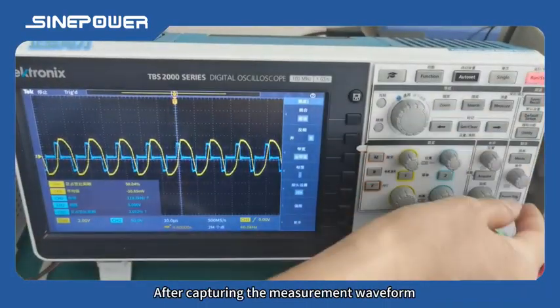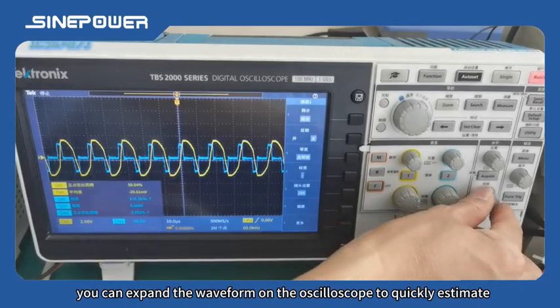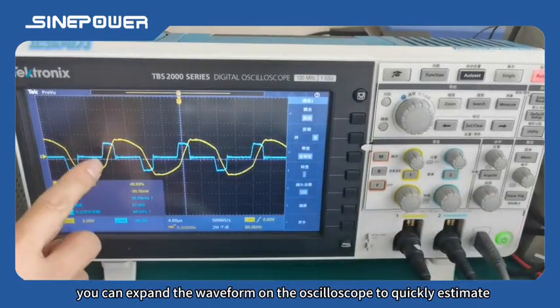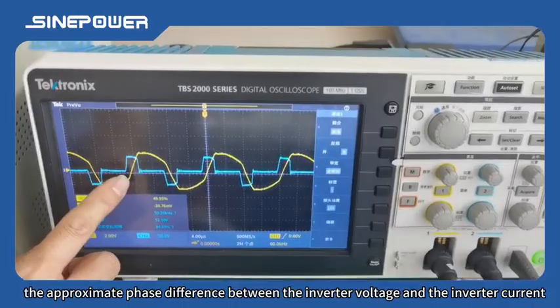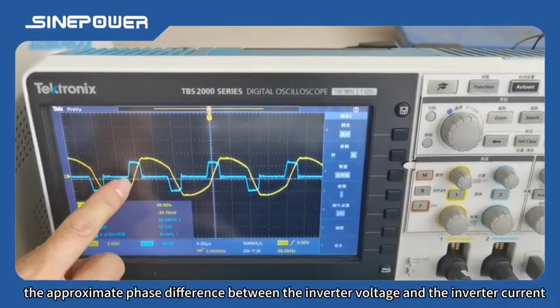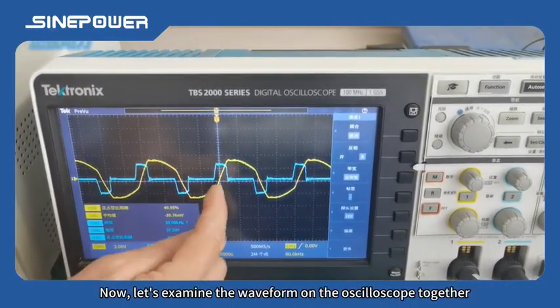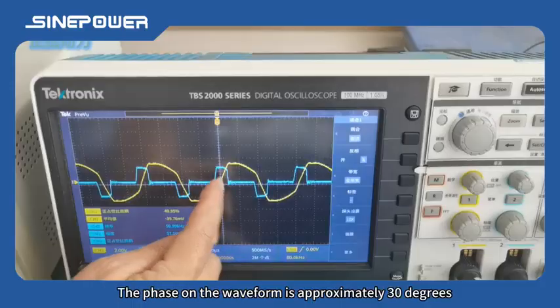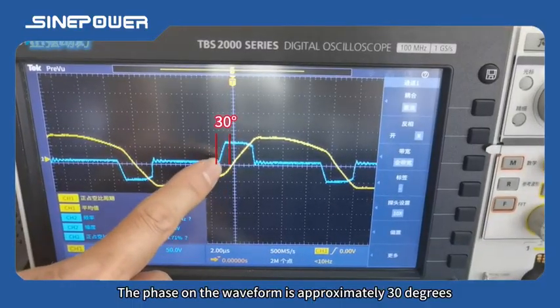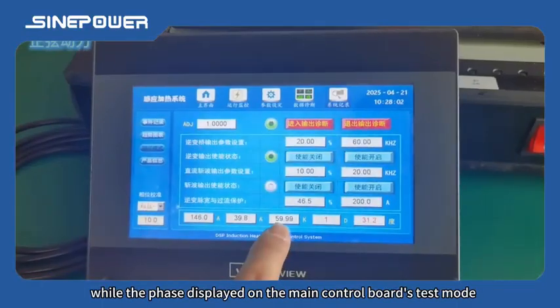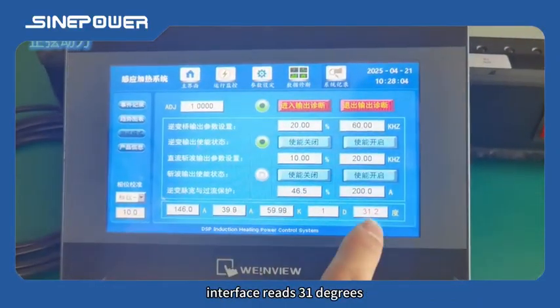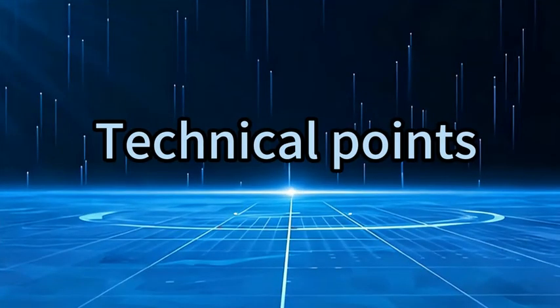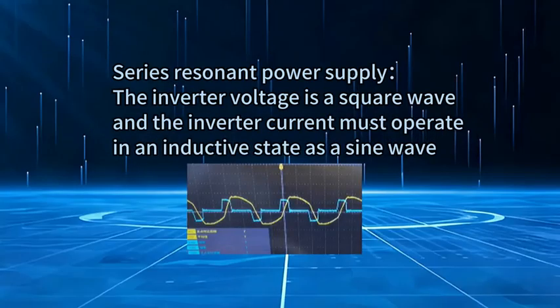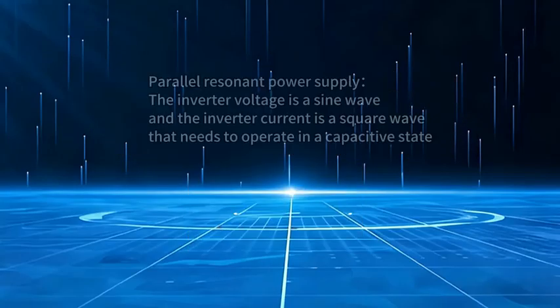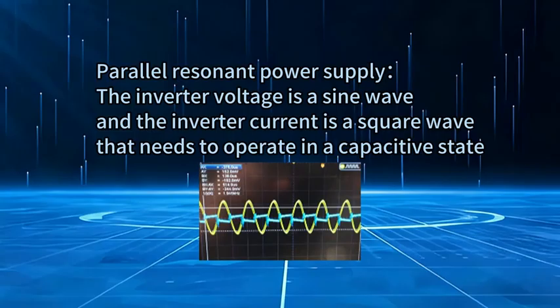After capturing the measurement waveform, you can expand the waveform on the oscilloscope to quickly estimate the approximate phase difference between the inverter voltage and the inverter current. Now, let's examine the waveform on the oscilloscope together. The phase on the waveform is approximately 30 degrees, while the phase displayed on the main control board's test mode interface reads 31 degrees. Series resonant power supplies operate in a weakly inductive state, while parallel resonant power supplies operate in a weakly capacitive state.